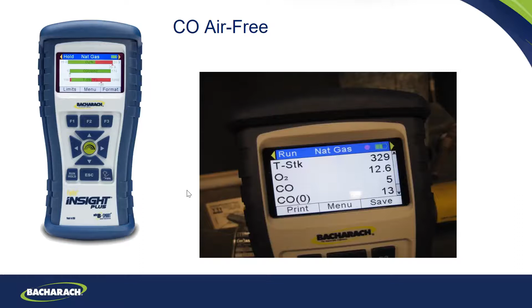Because if I had 100 ppm raw CO and I diluted it with 20% excess air, it would give me a different reading than if I diluted it with 50% excess air. So I could run a boiler, and if I knew someone was coming to test it, just add more excess air and lower that CO. So they're saying, no, we don't want to do this. So they came up with CO air-free, which takes the oxygen out. You need a combustion analyzer to do this because you need that oxygen sensor.